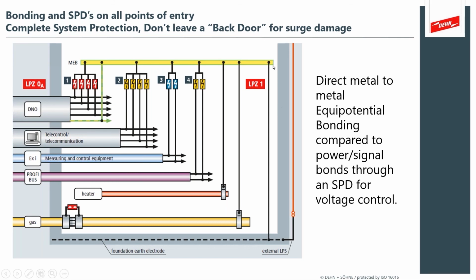And an illustration like this is really nice because it shows you've got your earthing system bonded to the master ground bar, the master electrical bar, the master earthing bar. Well, that's bonded to the earthing ring, buried and separate from the lightning protection down conductor. Remember, you don't want to bond into your lightning down conductor with sensitive electrical equipment. You want to have a dedicated bonding connection into the earth ring. Now you look at things like your black gas pipe. Well, that pipe is bonded to that earth bar. Or you might have things like copper pipes in your structure. Those copper pipes are also bonded to the master bar.